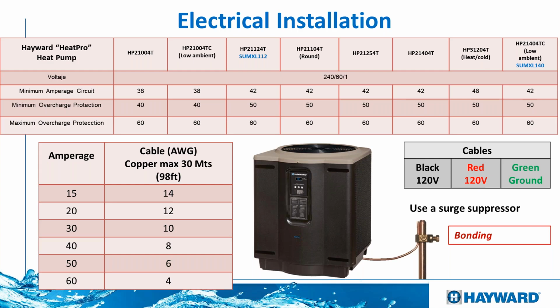And also, I always tell people, please follow the rules of the colors of the wire. If the wires are hot, if they're 115 volts or so, the colors need to be by code either black or red. Black and red is going to make the difference between the first part and the second part of a 2-pole breaker. But at least use 2 blacks or 2 reds, just so we can say that they are hot wires. As we know, neutral is always going to be white. In the case of a heat pump, we don't need neutrals, but the white color always means that it's neutral. And then the green one always means that it's a ground.